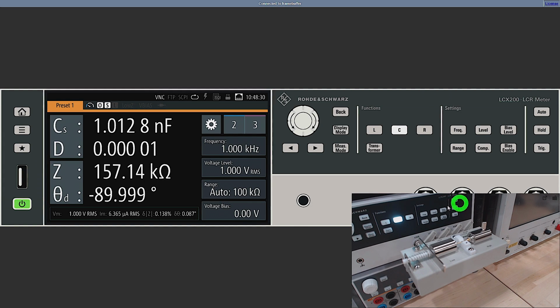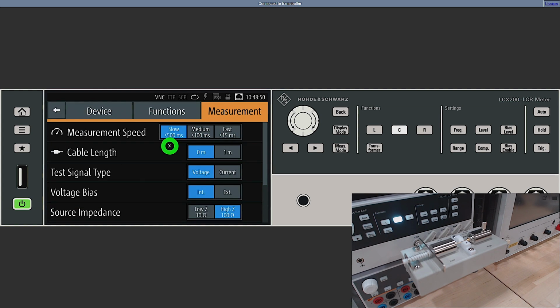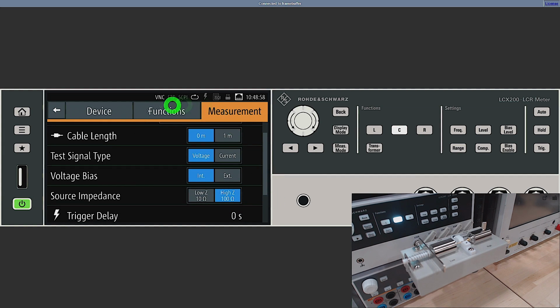So next I have the surface mount test fixture directly attached, and I would like to perform some binning on some surface mount capacitors that I have. There's one already inside of the fixture, and you can see we're measuring about 1 nanofarad. And these are capacitors that have a 5% tolerance, nominal value is 1 nanofarad. Now one thing I noticed that we don't have in the firmware is any means of averaging, even though we do have measurement speed, slow, medium, and fast, but this is a trade-off between measurement speed and accuracy repeatability. It's not an averaging function, so that definitely should be added to the firmware, and it is pretty important to do averaging, especially during binning.